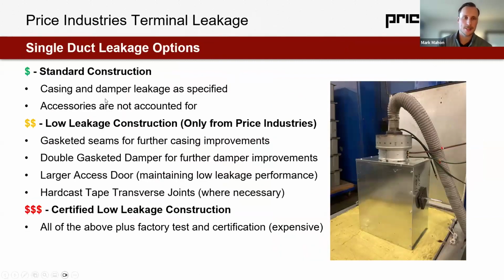My last takeaway slide here is the standard construction is most affordable for upfront cost. The casing and the damper leakage would be as specified. Accessories are not accounted for, but you can specify access door leakage. Low leakage construction is another option, which is actually only from price. So this gasket seams for further casing leakage improvements. We have a double gasketed damper. We have larger, lower leakage access doors, and we hard cast tape seams and transverse joints whenever it's necessary. However, this doesn't test in the factory. It's the construction without the testing. So it comes at a lower cost. This is my recommendation for what I think should be specified. If I was a design engineer, this is what I would be specifying: a low leakage construction without the factory certification. Finally, the factory certification is gold plated maximum option of the above plus factory test and certification.